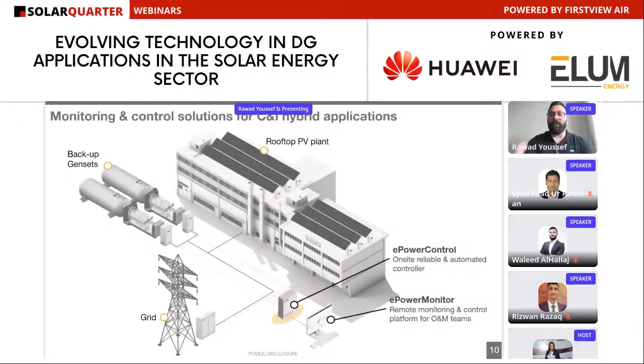Going to the off-grid side, here's an example with a genset plant, PV, and BSS system. In these cases we use our microgrid or PPC controllers, with basically the same concept - the controller is connected through Modbus with the different equipment and can provide several features, depending on each project and how the client or EPC wants to manage the system. What we provide is an energy management system that can manage between these different sources.